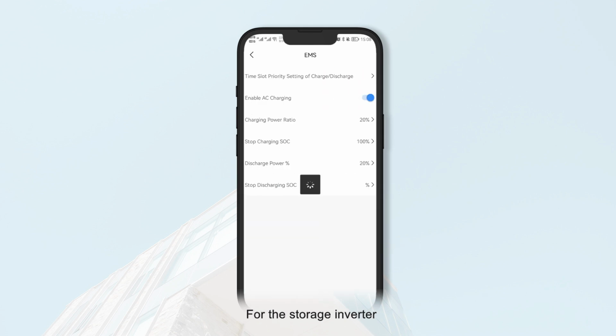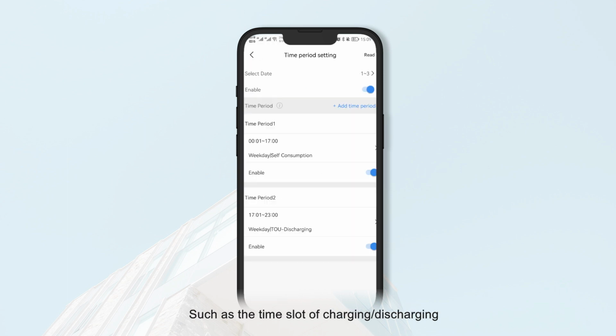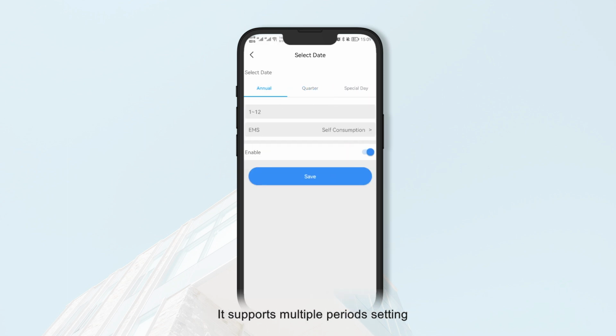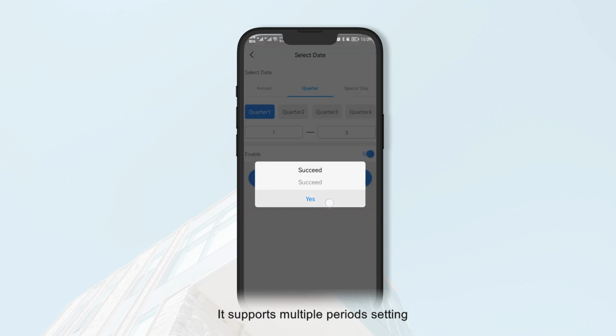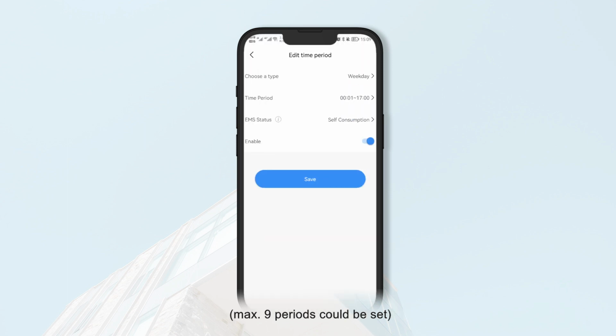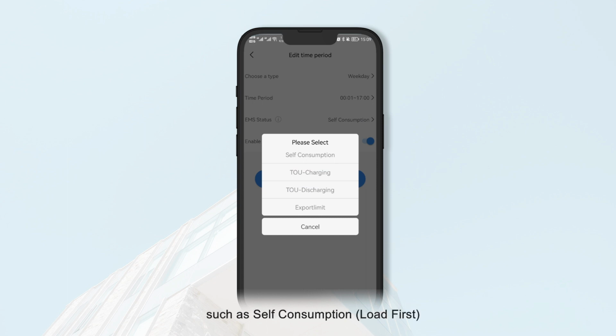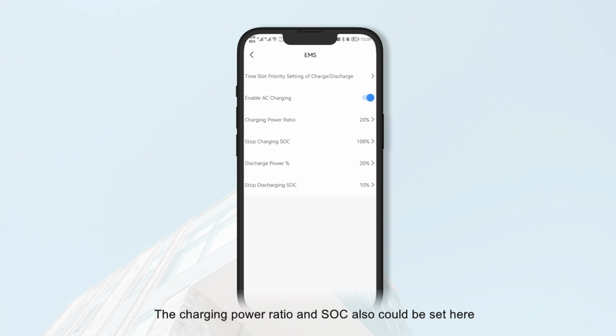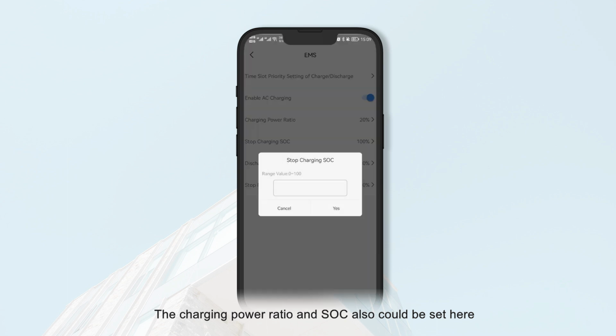For the storage inverter, there's an EMS channel used to set battery mode, such as the time slots for charging and discharging. It supports multiple period settings, with a maximum of 9 periods, and multiple modes such as self-consumption, load first, TOU charging, battery first, TOU discharging, and grid first. The charging power ratio and SOC can also be set here.